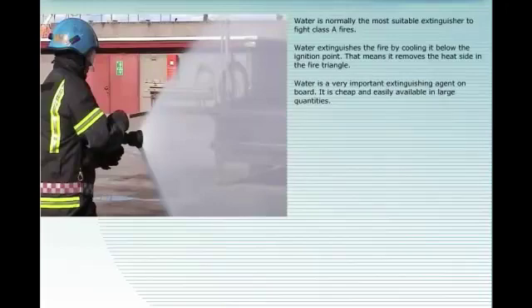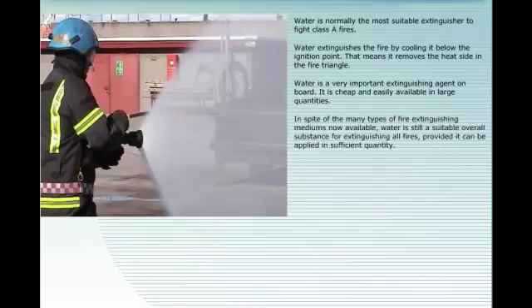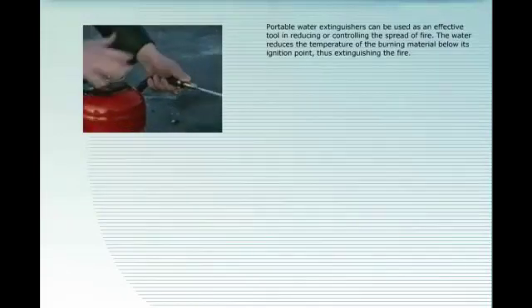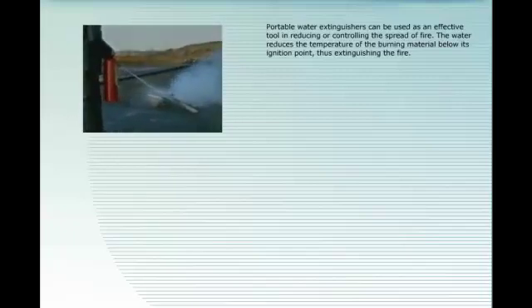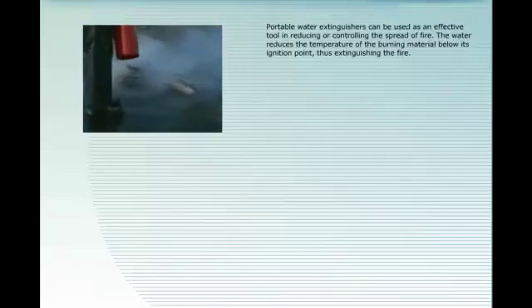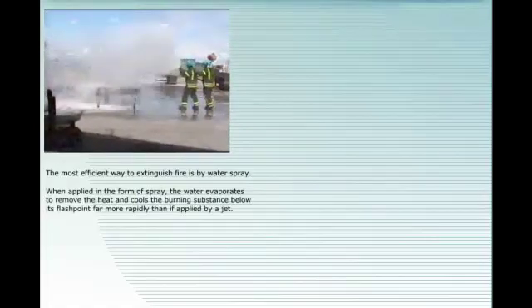Portable water extinguishers can be used as an effective tool in reducing or controlling the spread of fire. The water reduces the temperature of the burning material below its ignition point, thus extinguishing the fire. The most efficient way to extinguish fire is by water spray. When applied in the form of spray, the water evaporates to remove the heat and cools the burning substance below its flash point far more rapidly than if applied by a jet. In addition, the wide angle provided by the spray will protect the firefighter from the heat of the fire.